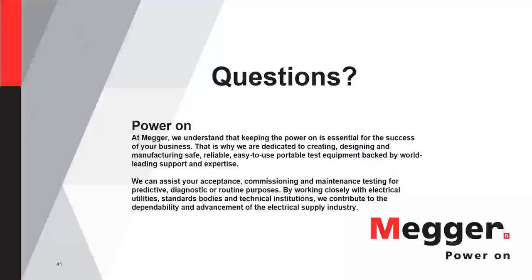And again, if you're talking about ripple voltage and ripple current, the most predominant source of that would be the charger. Typically, like I said, in substation applications, the charger would be your primary culprit. If you saw some very high ripple on big flooded batteries, typically it's going to be a bad rectifier in the charger. But in telecom applications, you may see things coming from the load at higher frequencies causing that, and that's where a spectrum analyzer can come in handy. Okay, thank you, Andy. Next question.